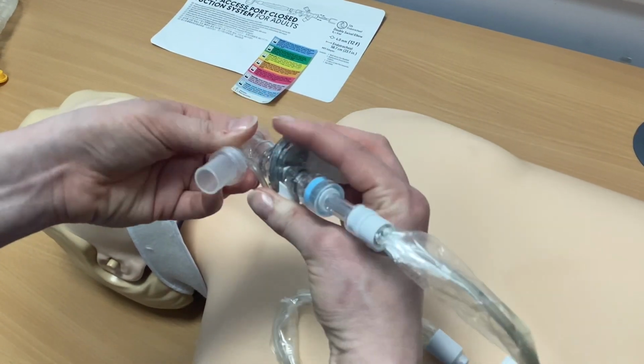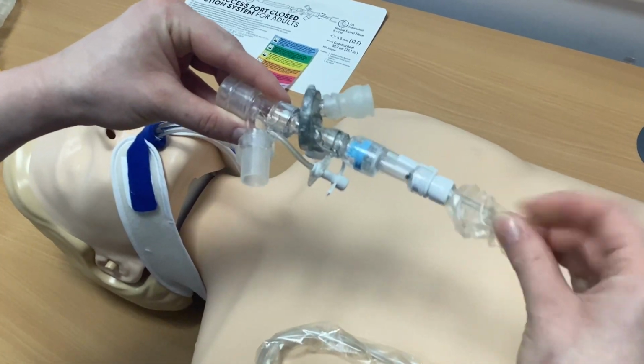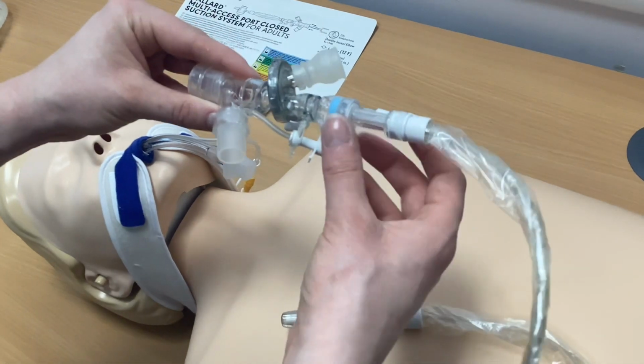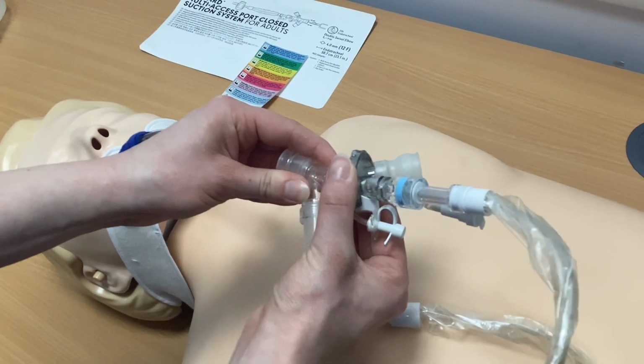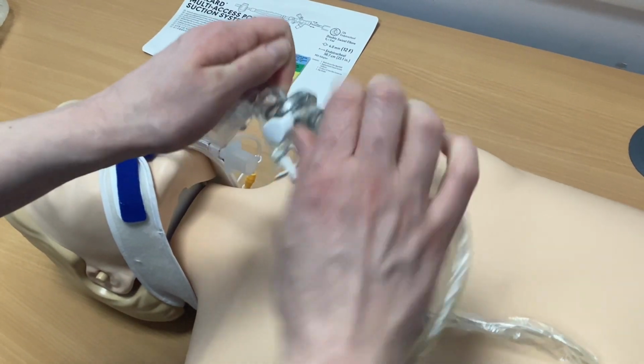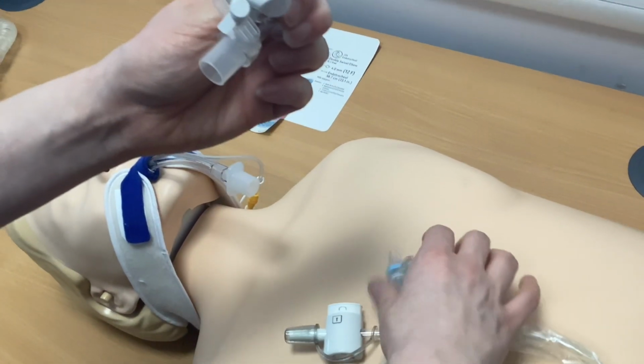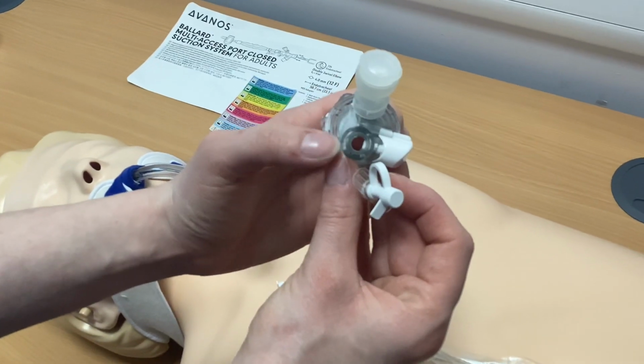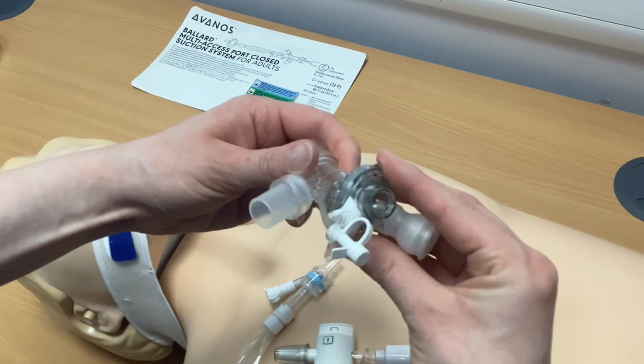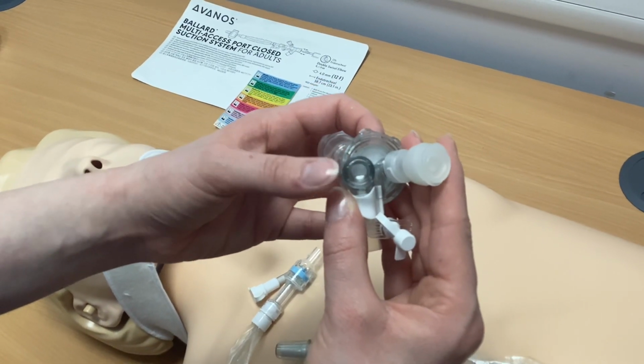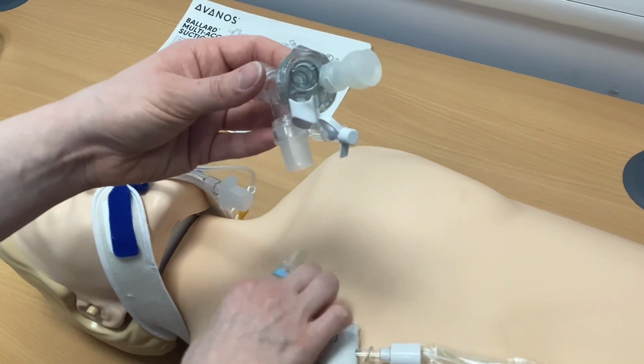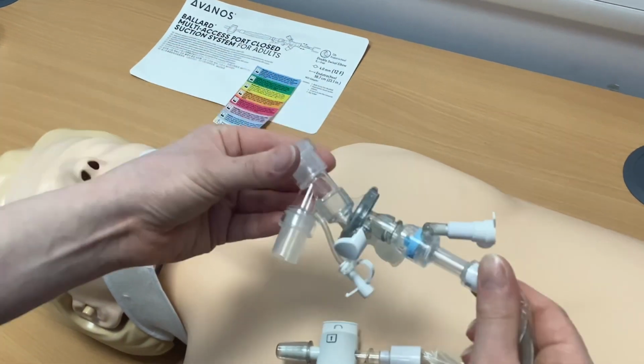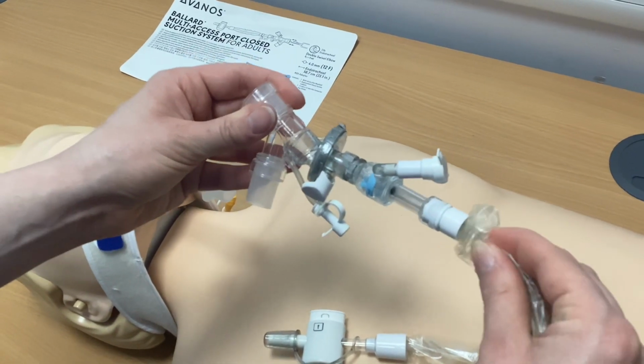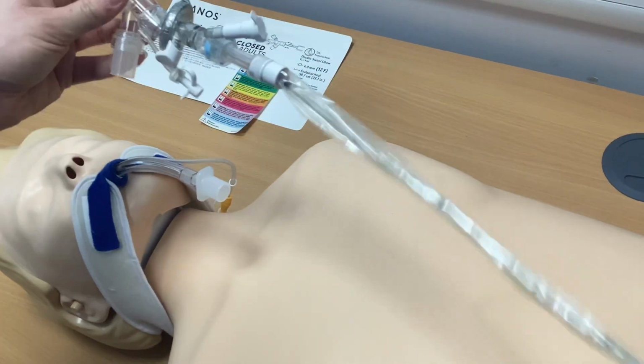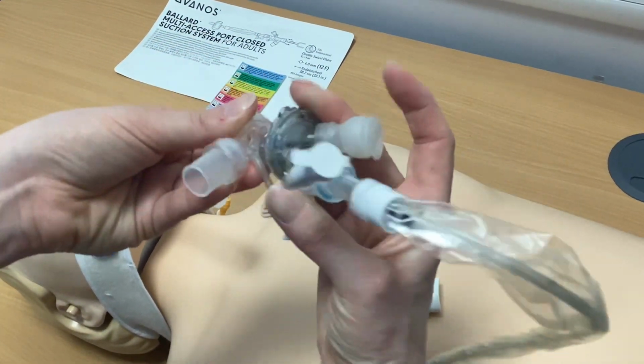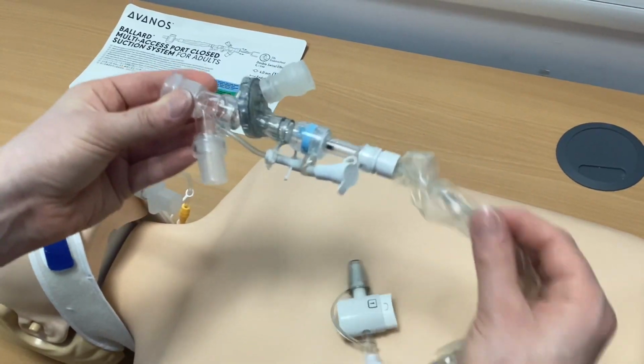So currently we are in the suction inline, so we can pass the suction catheter down. This multi-access port will allow us to spin into a neutral position. So if I show you the difference, I've removed my suction catheter and you can see that there is a hole just here. When I'm pushing this into neutral, this hole is blocked off and is allowing the PEEP to stay inside, which means that you could bring your new suction catheter and connect this without losing any PEEP for your patient. However, it's important to make sure that you're then twisting the site back towards open again, so that this is all in line once again, so that then you can use your suction catheter again.